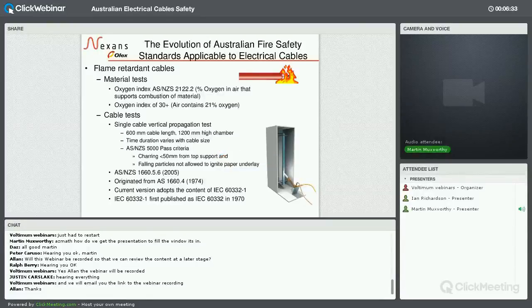The next series of tests that I'm going to describe talk about flame propagation of the cable itself, not materials, but the cable itself. The first one is a fairly simple single cable test. All cables made to AS5000, for example, need to pass that test. The test method is detailed in AS1660 Part 5.6, and that's linked to the IEC standards, for instance, IEC 60332 Part 1. And those standards date back a long way. I mean, that standard was first published in 1970. So, as you can see, the standard is quite well established.